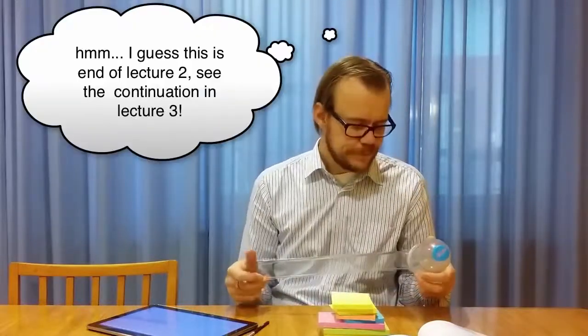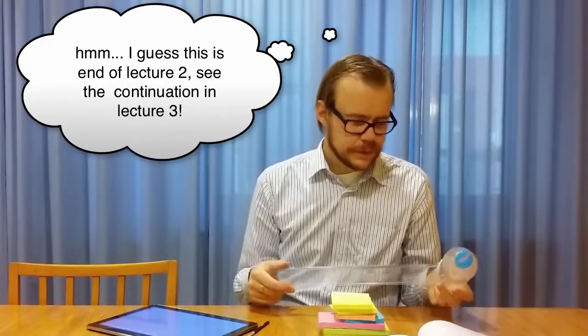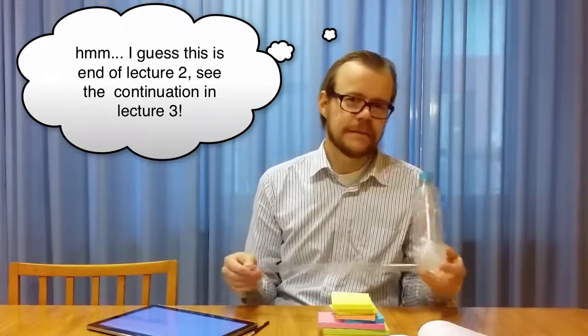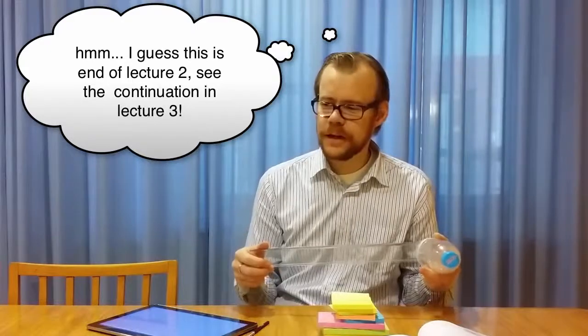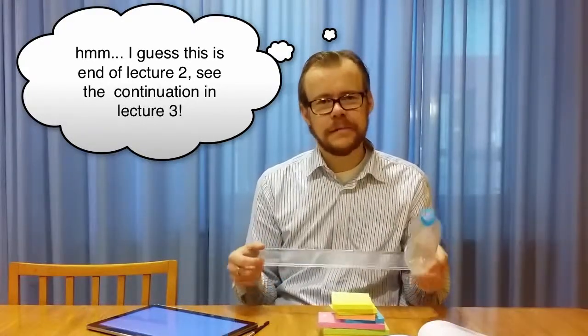So in non-contact mode, you have this vibrating tip that goes above the surface like this. And when it comes close to an obstacle, the resonance frequency will change. It's hard to show, but I can hold it closer. Then the resonance frequency will increase like this due to these interaction forces. And when I come down out in the opening here, it will go back down again. So that is how you do it when you use this non-contact mode. I think these few techniques that I showed you now sort of give you the most general idea behind this.